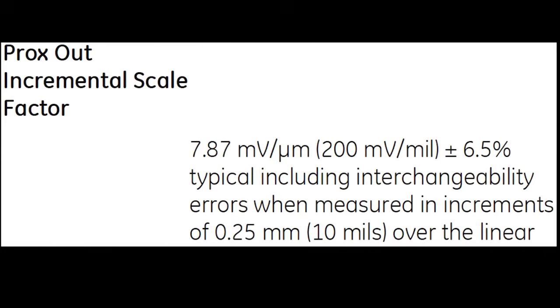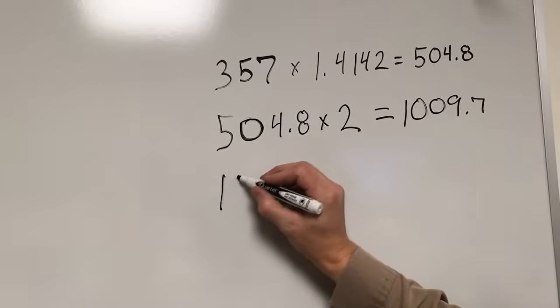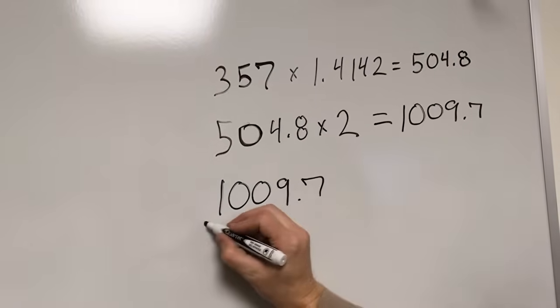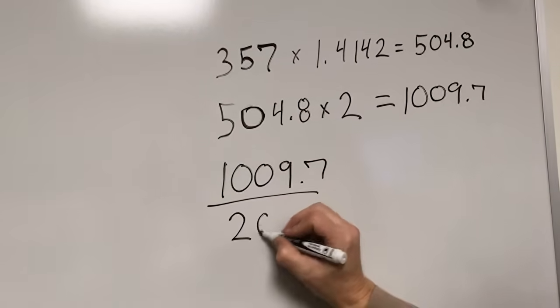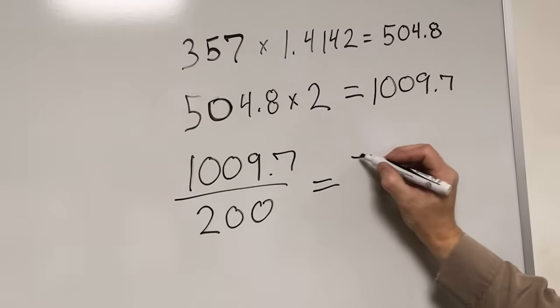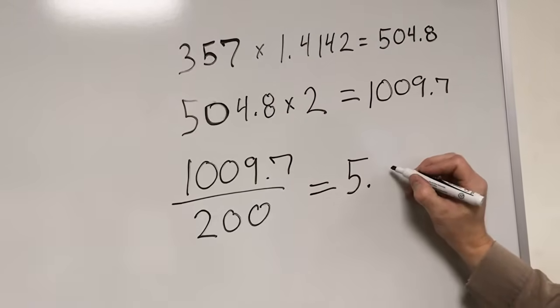Now, we must apply the incremental scale factor, or ISF, to this measurement to convert the voltage change to a change in distance. If you want to determine the amount of travel the proxy probe detected using this ISF, you would divide the peak-to-peak voltage by 200. The number you get will represent the amount of distance the assembly measured.